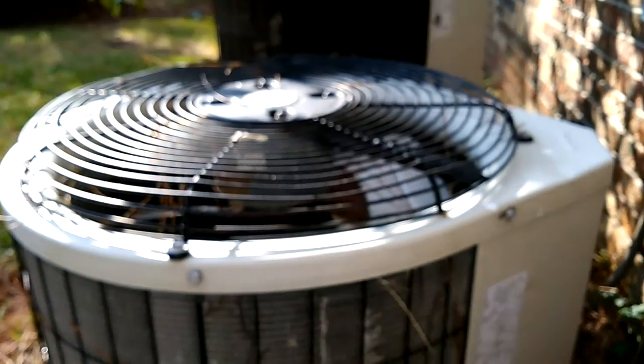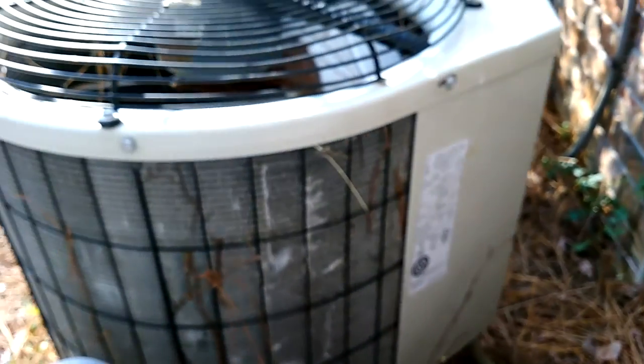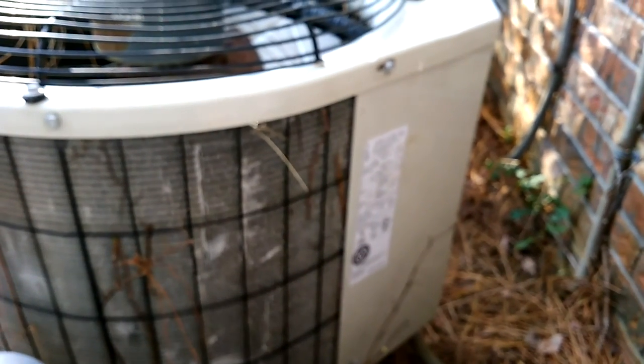I came out here to see why it's not producing any heat. Even without opening up the panel, I checked the valve here. Stuck my screwdriver in there and pushed the Schrader valve. Got nothing. So it's completely out of charge.